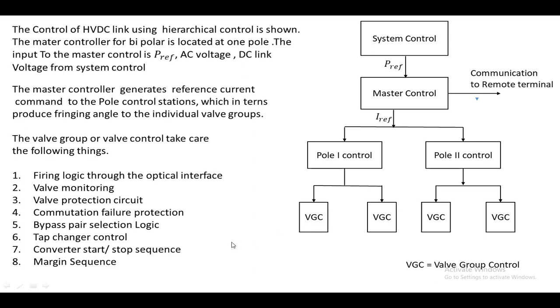Next is communication failure protection. Sometimes there is a communication failure between the rectifier station and the inverter station, or between rectifier stations — that is also taken into consideration by the valve group control. Next is bypass pair selection logic, followed by tap changer control. The transformer supplies power to the rectifier and inverter stations, and the tap changing on the transformer is adjusted depending on how much AC voltage is required — that is also handled by the VGC. Finally, converter start and stop sequence — whether to turn the converter on or off — is also considered by the VGC.